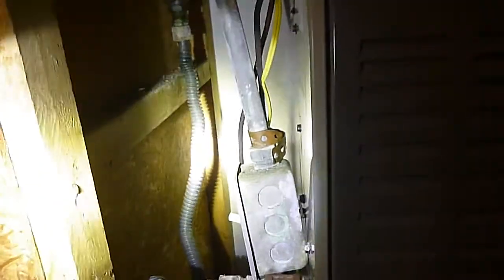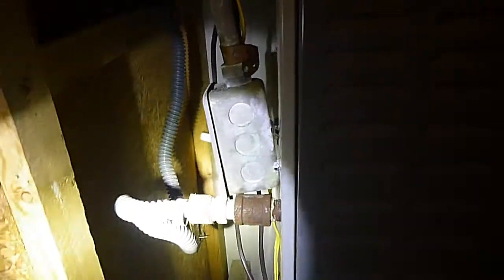It's an old style brass gas valve. It takes a wrench to turn it off. These gray connectors, you have one on each indoor air handler, that's 2. You have one on each water heater, that's 4. All of your gas appliances have this gray flexible connector, and that's been out of commission for who knows how long. 20 years. That's not been acceptable.